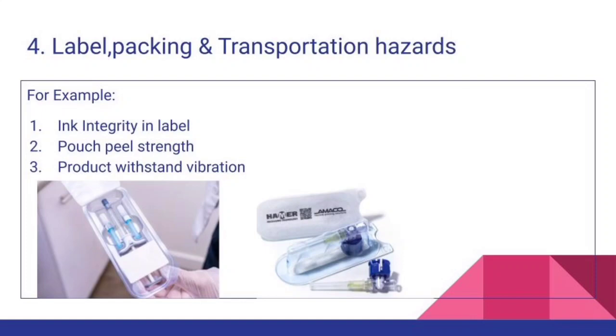The next type of hazard is label, packing, and transportation hazards — for example, ink integrity in the label, pouch seal strength of the packing pouch, and the product withstanding vibration if it is in a carton or corrugated box packing during transportation.